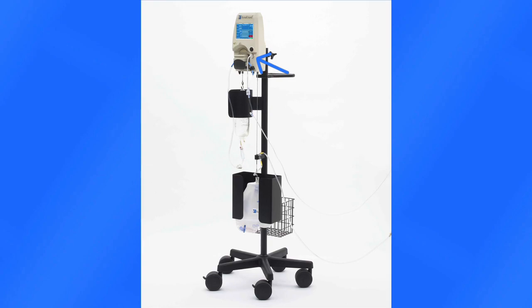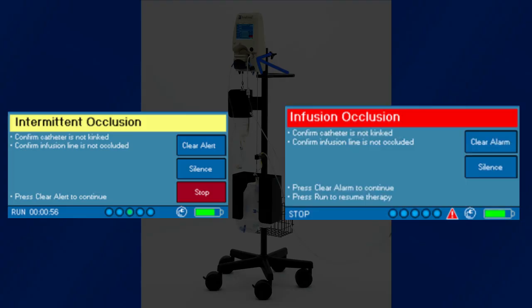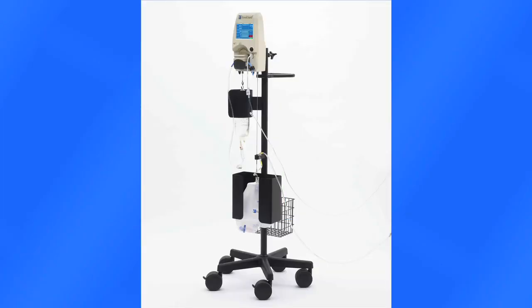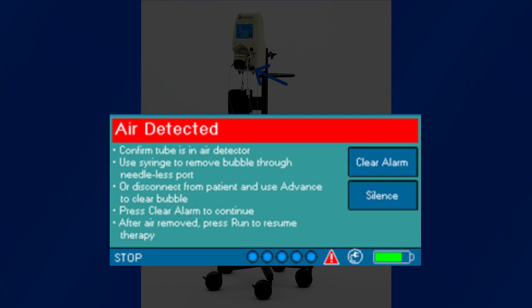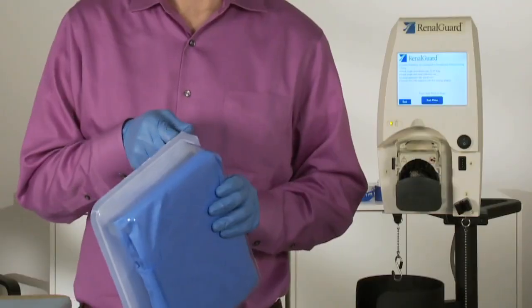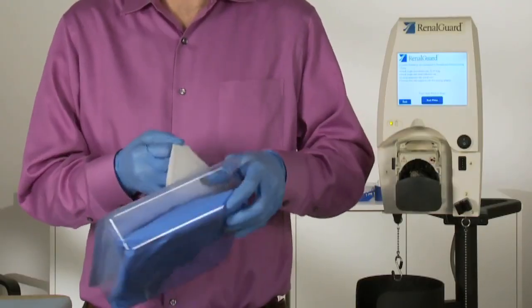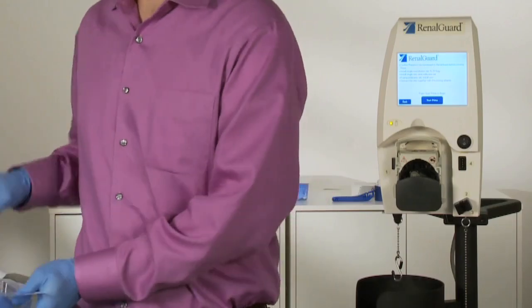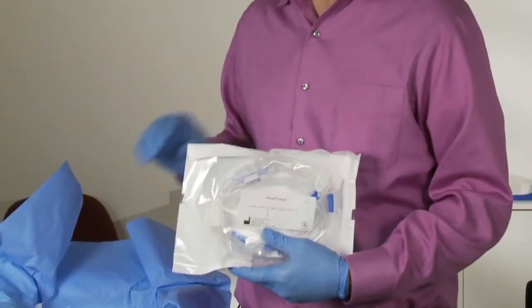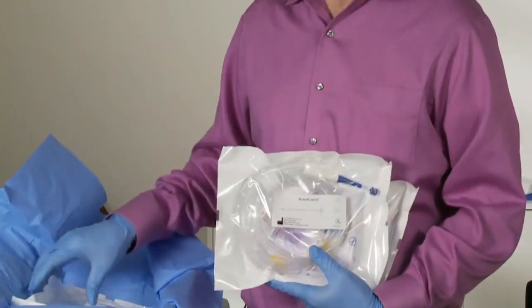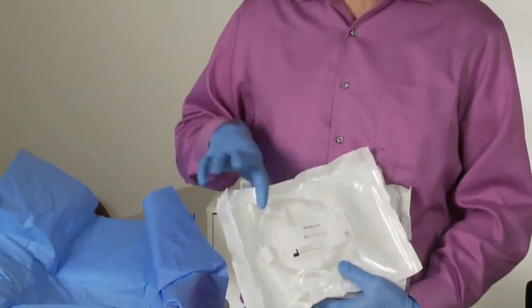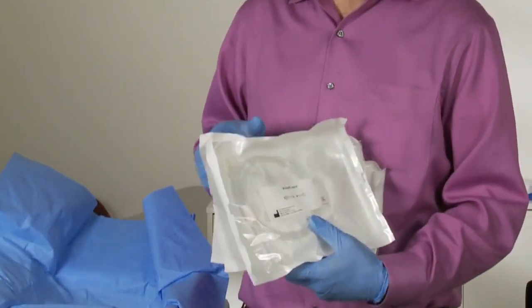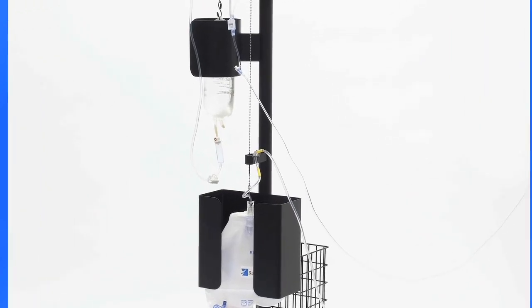The pressure sensor will trigger an alarm for partial or complete infusion line occlusion, and the air detector will trigger an air bubble alarm and will pause the therapy until the issue is resolved and therapy is restarted by the user. Each cardiac surgery patient requires a sterile single-use set, which includes an infusion set, a urine collection set, and a urine line extension to be used if needed based on the OR setup. The infusion set connects to the infusion bag.